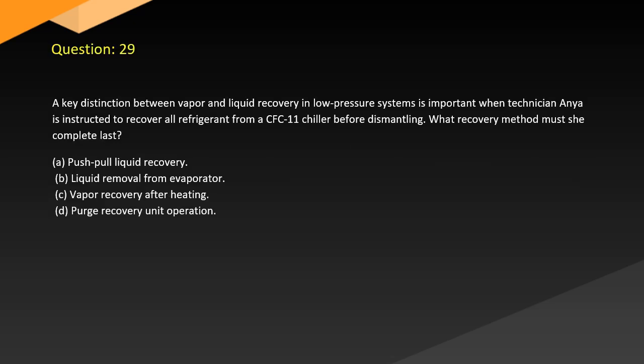Question 29. A key distinction between vapor and liquid recovery in low-pressure systems is important when technician Anya is instructed to recover all refrigerant from an R-11 chiller before dismantling. What recovery method must she complete last? A. Push-pull liquid recovery. B. Liquid removal from evaporator. C. Vapor recovery after heating. D. Purge recovery unit operation.